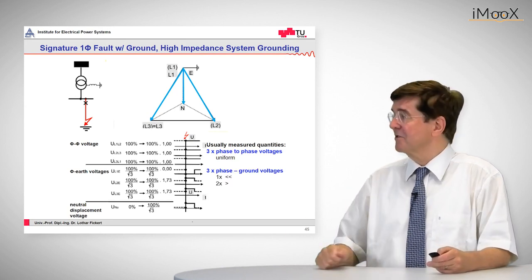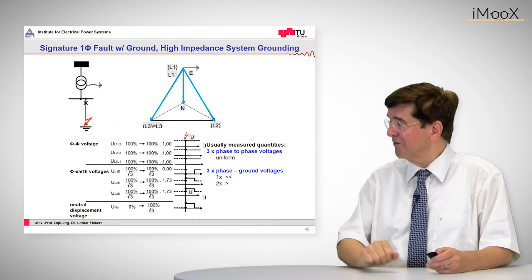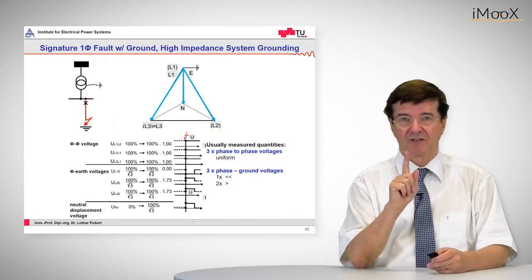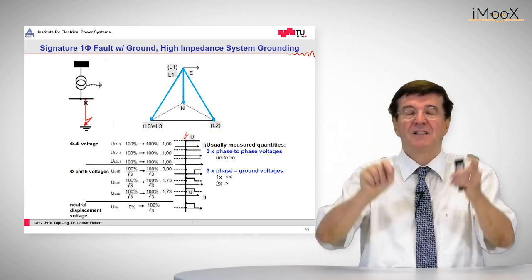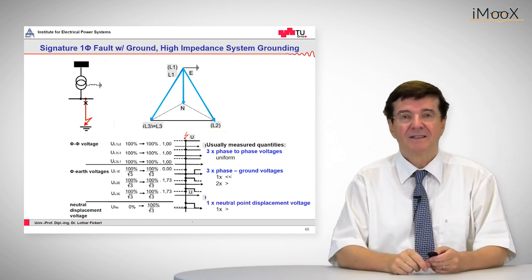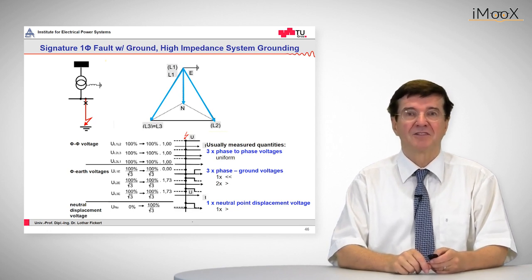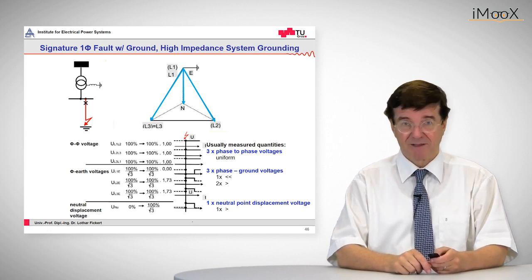But when it comes to the second set of voltages, the phase-to-ground voltage, we see that one voltage collapses and two voltages rise. And another indication for involvement of ground, we have a very substantial neutral point displacement voltage.